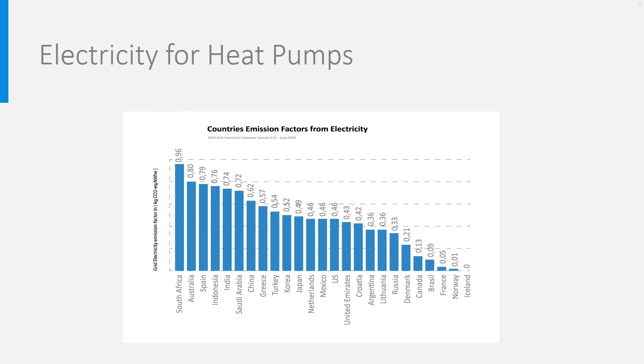In both cases, we assume that 3000 kilowatt-hour electricity is used annually to power lighting and household appliances. The annual heating demand in the well-insulated house is 15,066 kilowatt-hour. In the passive house, it is only 5,014 kilowatt-hour. If we use a heat pump with seasonal COP 4, we then need 15,066 divided by 4, which is 3,767 kilowatt-hour electricity for heating in the well-insulated house, while we come to 1,254 kilowatt-hour in the passive house. So in total, 6,767 kilowatt-hour electricity is needed in the first version and 4,254 in the passive house version.